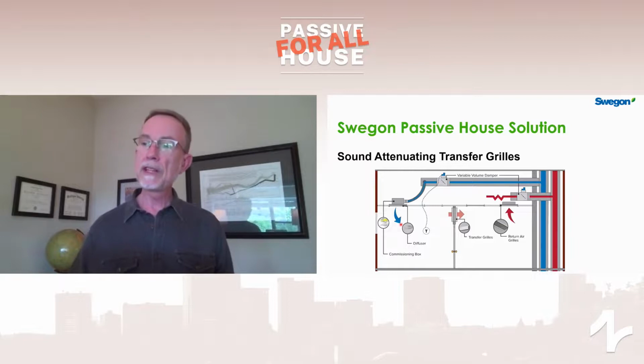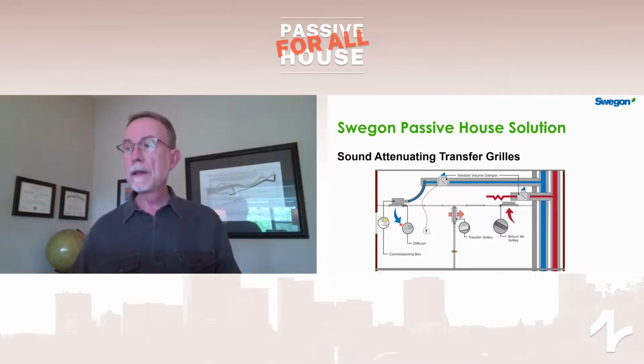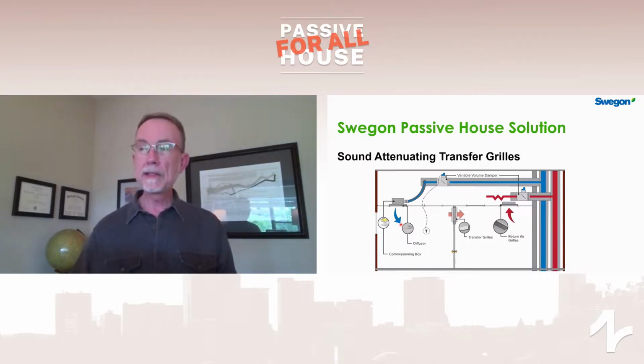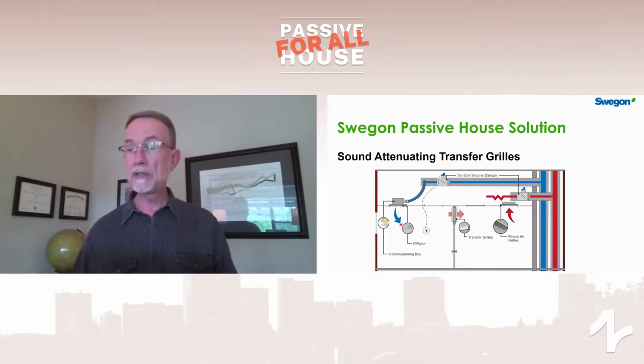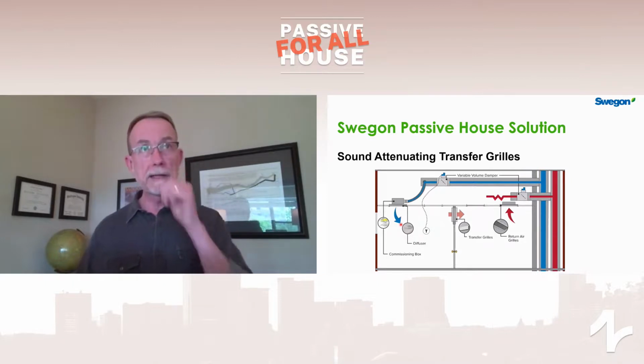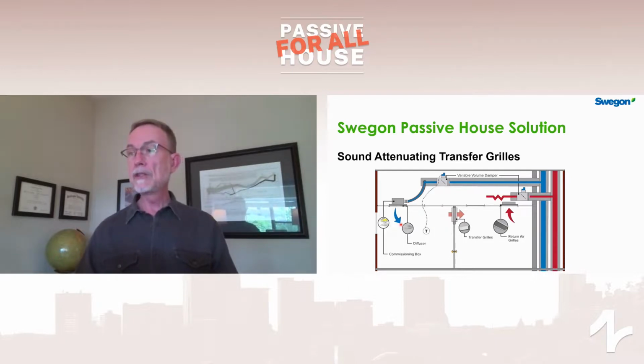In this case, we're kind of representing an office space. The air would be delivered into the office where the occupant is. In this case, the transfer grill allows the pressure of this room, being slightly higher, to blow air through the transfer grill into the corridor, and then the corridor has the return air grill. This prevents you from needing to have duct going all the way over into this office space. And over an entire building, a substantial amount of external static pressure can be avoided so that the energy recovery ventilator doesn't have to work so hard and save energy.